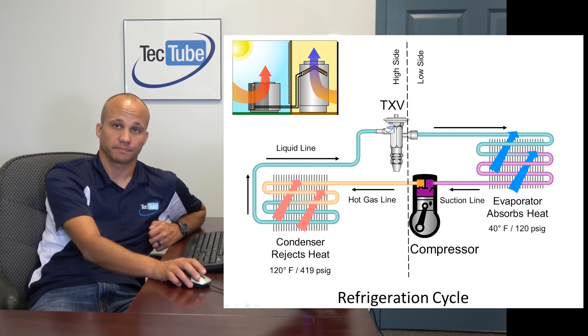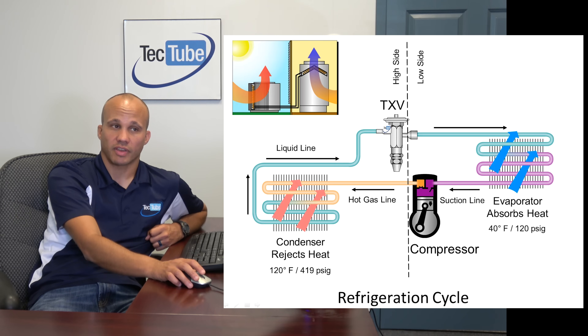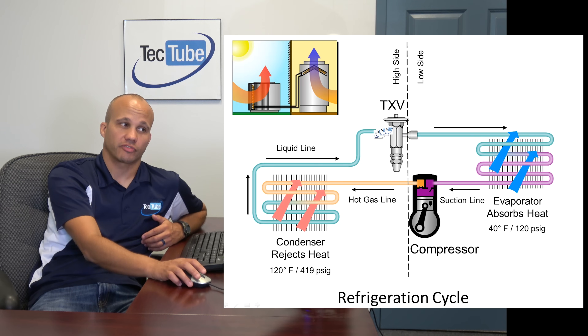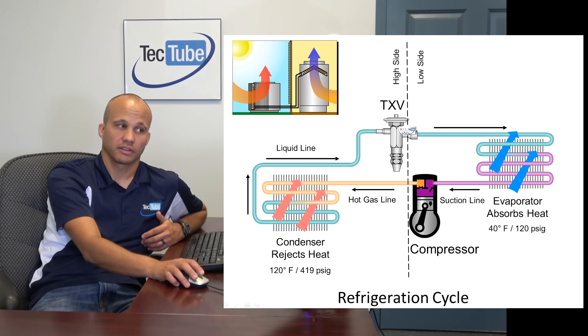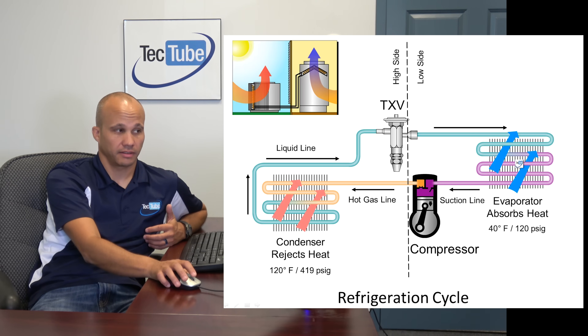The refrigerant condenses back to a liquid, which is why we call this the liquid line, and it travels over to the TXV. TXV stands for thermal expansion valve — it's a metering-type device. Older systems had fixed orifices or pistons; nowadays almost everything has a TXV. Its job is to meter the refrigerant as it enters the evaporator and to change the pressure from high back down to low, since it's the opposite of the compressor. Then the refrigerant goes back into the evaporator coil at lower pressure, where it can begin absorbing heat again. That's the basic refrigeration cycle.